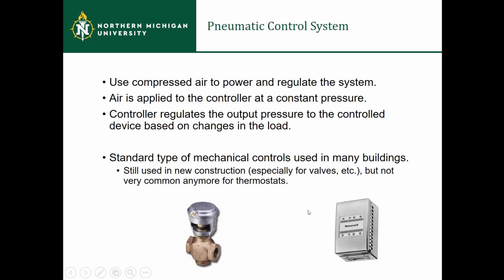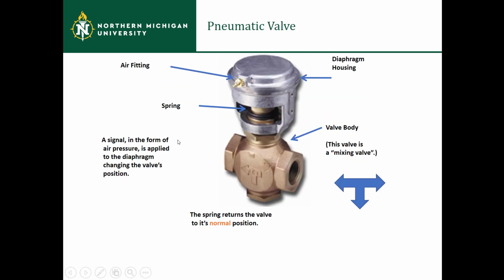Pneumatics are very common, especially in older buildings, but you'll still see quite a bit of them. They use compressed air to power and regulate the system. The air is supplied to the controller at a constant pressure. The controller regulates the output pressure to the control device based on the changes in the load. So this is the standard type of mechanical controls that we use in the building. Like I mentioned, it's still used in new construction, just very sporadically. Some of the people I use for my guest lectures that come in and talk about control systems still mention you'll see them on specs once in a while, even in brand new facilities, but not very common. So they're using this pneumatic valve here where a signal in the form of air pressure is applied to the diaphragm, which is up here in the housing, and that changes the valve's positioning. They're actually quite accurate just because they're dealing with air pressure.